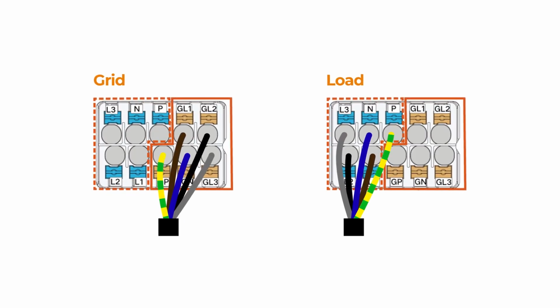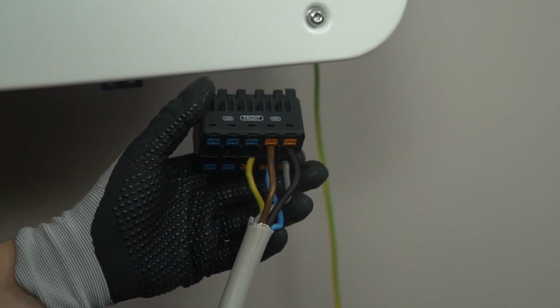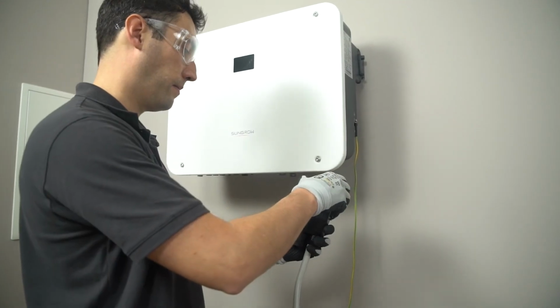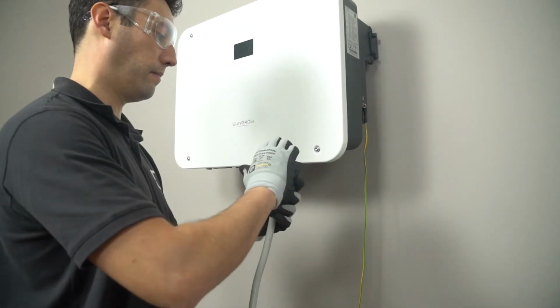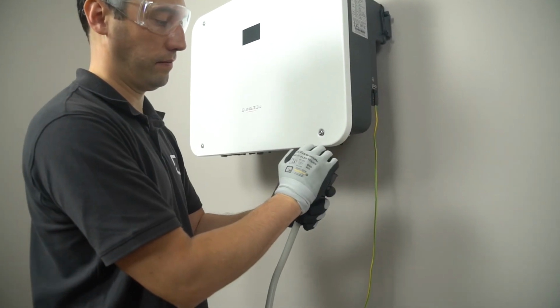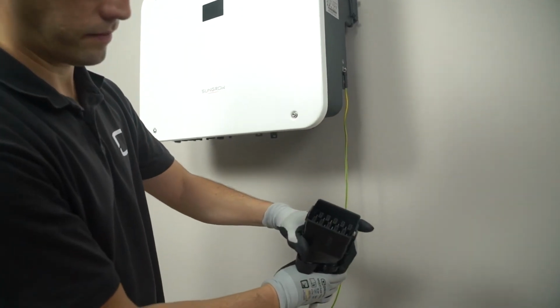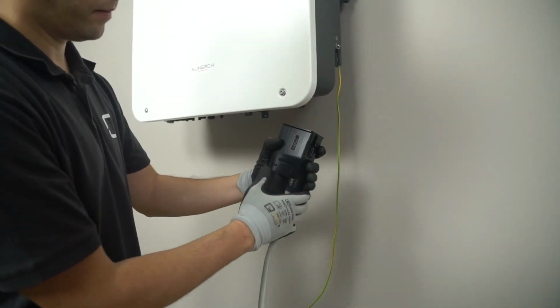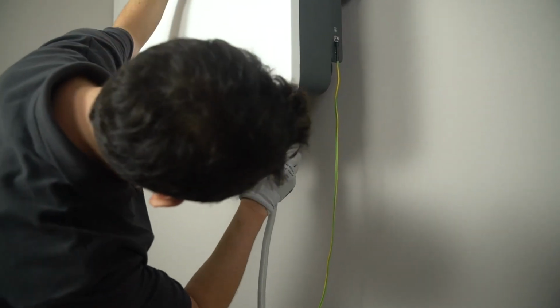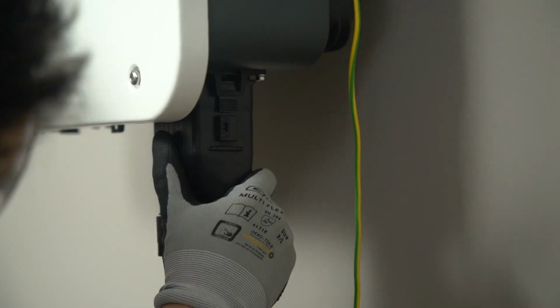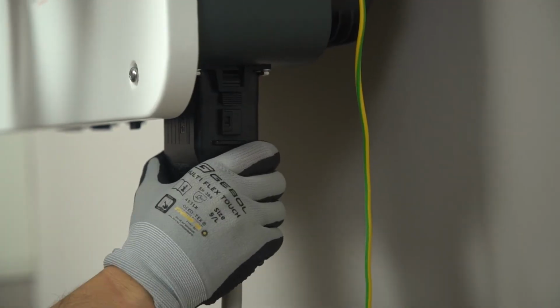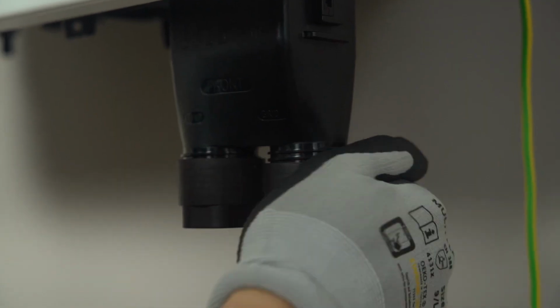After finishing wiring, make sure the cold-pressed terminal does not protrude from the outside surface of the AC terminal. Ensure that the wires are securely placed by slightly pulling them. Insert the AC connector into the grid and load terminal on the inverter until you hear a click. Tighten the swivel nut to the housing. Lock the AC connector using a slotted screwdriver.